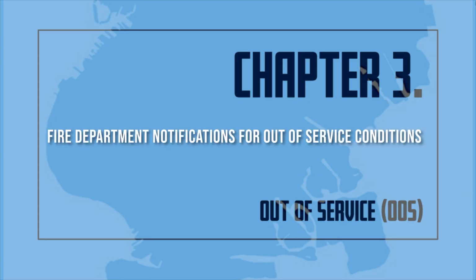Fire department notifications for out-of-service conditions. A. For a planned removal from service, no notification to the fire department is required, provided the system will be returned to service within an 8-hour period, and when all other fire protection systems in the building, standpipes and alarm systems, are fully operational.